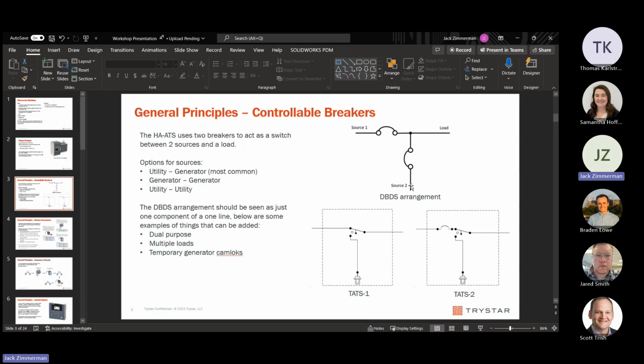You can also have two generators, which is often seen at remote sites. A mining site, for example, may not have utility power because it's too expensive to bring out there, and you don't want to run your generator 24/7 for too long. So what they'll do is run one generator for 2 weeks, then have the automatic transfer switch over to the other generator for 2 weeks, doing maintenance throughout the week on the one generator, constantly keeping them online. There's capability within the controller that we can program to do a timer like that - it directly supports this transfer of generators.